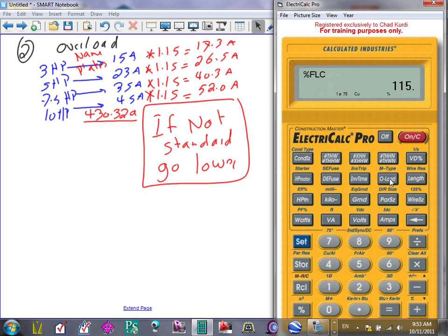Okay. Now I want to remind you, Ashley, that the overload is defaulted to 115. If your circumstances are different than 115, you cannot use this overload. Sometimes if the service factor is more than 1, like 1.15, you can go for 125%. So it really defaults to 1.15. For all practical reasons, that gets you there, but you have to be very careful though.